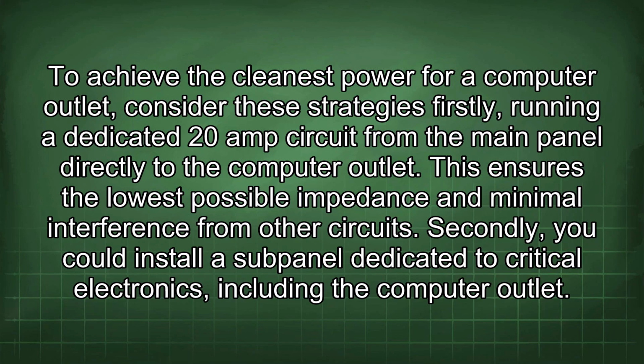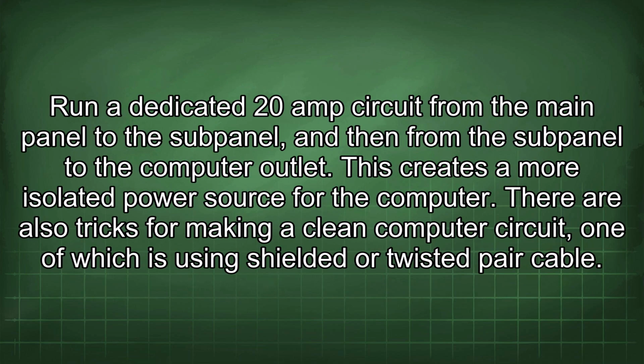To achieve the cleanest power for a computer outlet, consider these strategies. Firstly, running a dedicated 20-amp circuit from the main panel directly to the computer outlet. This ensures the lowest possible impedance and minimal interference from other circuits. Secondly, you could install a subpanel dedicated to critical electronics, including the computer outlet. Run a dedicated 20-amp circuit from the main panel to the subpanel, and then from the subpanel to the computer outlet. This creates a more isolated power source for the computer.